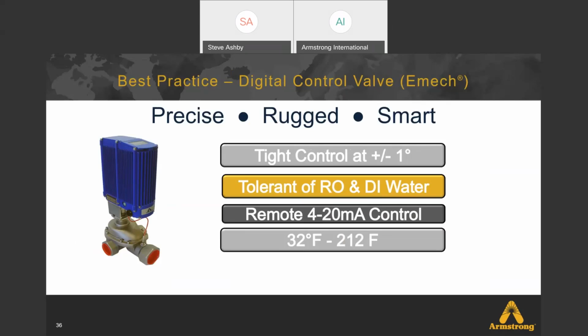On the top of the actuator, you can see there's a keypad. You can set the temperature there at the valve, or you can do it remotely by a 4 to 20 milliamp signal. You can control water temperature from 32 to 212 degrees. You can go to a full cold position or to a full hot. It doesn't have to be some equal parts of mixing. It can be full port, hot or cold, everything in between.